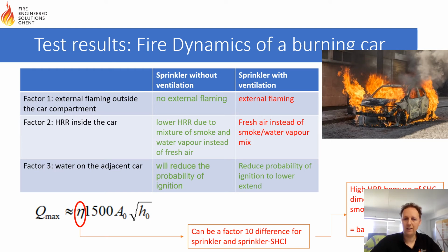So if you look at the maximum heat release rate that you will get in a burning car, we see that you could have 10 times larger heat release rate in a burning car with combined sprinkler and smoke and heat control system compared to only having a sprinkler system. So having a high heat release rate, because you want to have a smoke-free access till 15 meters in a combined smoke control and sprinkler case, is basically bad engineering. What you do is you create a higher heat release rate by imposing a higher velocity. So when we're looking at smoke and heat control systems in sprinkler car parks, what we should really be looking at is imposing a maximum velocity instead of a minimum velocity.